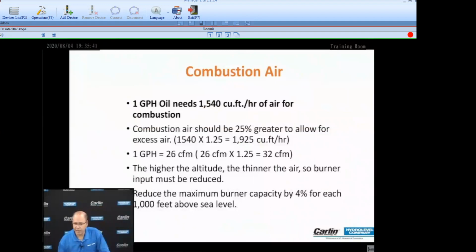Quantities of combustion air required for combustion. And there's a lot of misunderstanding again about where this air comes from. You know, where is your combustion air? A habit of mine is walking into a boiler room, and as soon as I walk in, I'm looking around, and where's the combustion air coming from? And if it's not there, I'm going to make a comment. But the comment I always get back is, well, it's always worked, so it must be coming from somewhere. Okay, I can accept that. It's always worked. I understand it. I live it too, but it doesn't make it right.